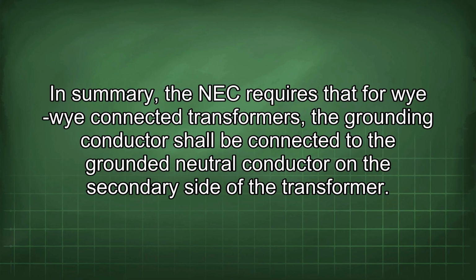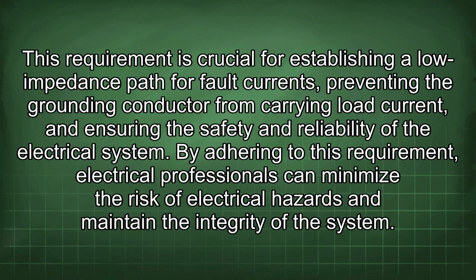In summary, the NEC requires that for Wye-Wye connected transformers, the grounding conductor shall be connected to the grounded neutral conductor on the secondary side of the transformer. This requirement is crucial for establishing a low impedance path for fault currents, preventing the grounding conductor from carrying load current, and ensuring the safety and reliability of the electrical system. By adhering to this requirement, electrical professionals can minimize the risk of electrical hazards and maintain the integrity of the system.